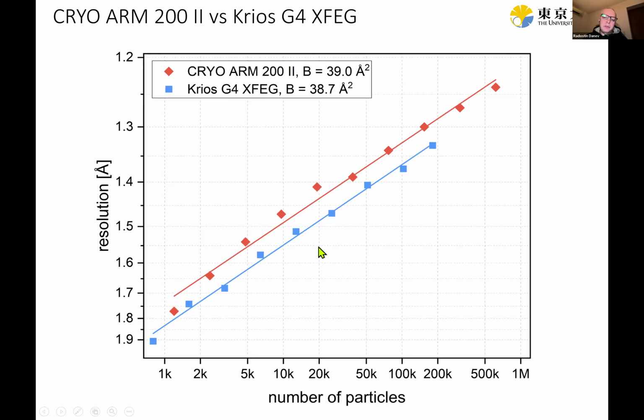And the second data set we evaluated was from our Krios version 4, Krios G4, which has a Schottky FEG. So it's not a cold FEG. With this one, we also got a B factor of 38.7, so virtually identical to the one of the Cryo-200 version 2. Now you see that the curves are a bit offset vertically, and this would mean that the overall signal-to-noise ratio in the data for all the spatial frequencies is a bit higher for the Cryo-200. Basically, it needs a bit fewer particles to reach a given resolution than the Krios dataset.